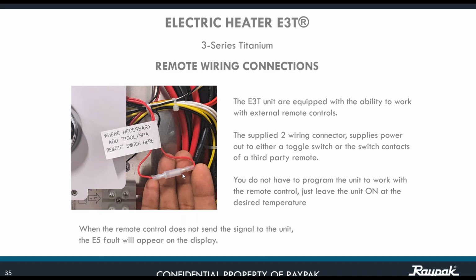Once you do that, you don't have to program the unit to work with the remote control. Just leave the unit on at the desired temperature. But my recommendation would be to take the unit all the way to 104. Why? Because most automation systems have their own temperature sensor. So if the automation system is the one commanding the actions, the unit is just going to obey whatever instruction is coming from the automation system.